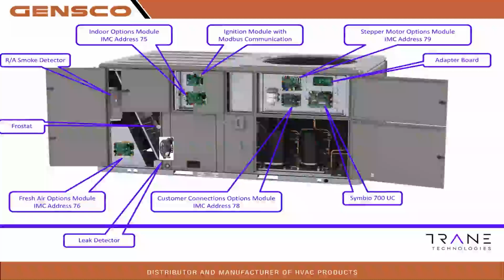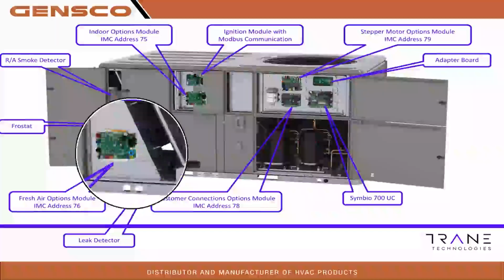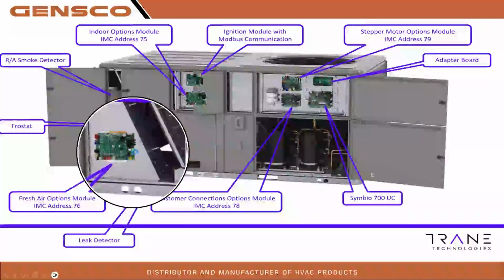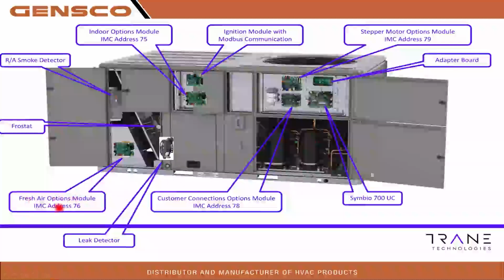This is a great picture I send to a lot of people when we're identifying what you have in your system. This is extremely important because we need to know what you have installed in there. So when we go to program, here's our fresh air options module. This is address 76. If you order it from factory, it's going to come with a little jumper harness right in the middle of it that's already addressed to 76. But if you're field installing the accessory, there are two dials right here. These two dials will be 7, 6, and that tells it that it's a fresh air options module. The same board can be used as your indoor options module, but you address it 75, and that will control your heat strip kit.